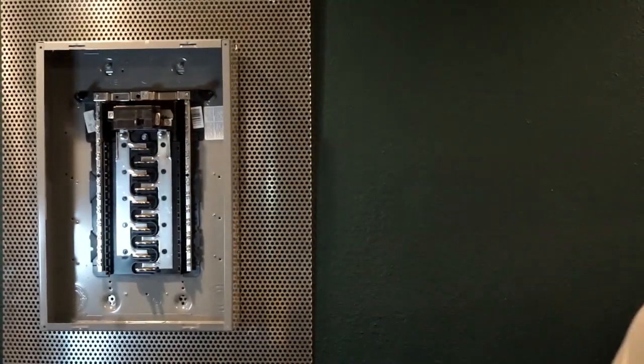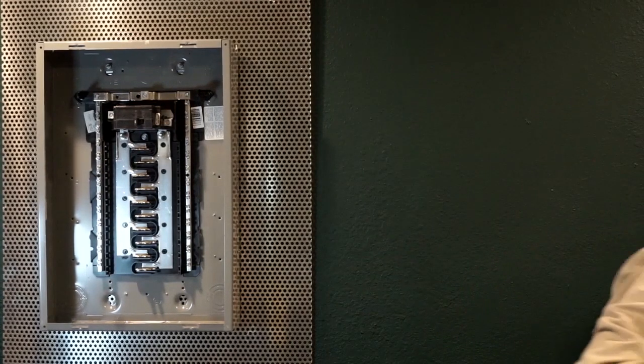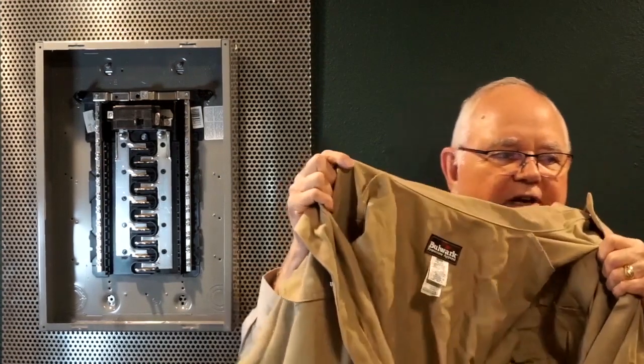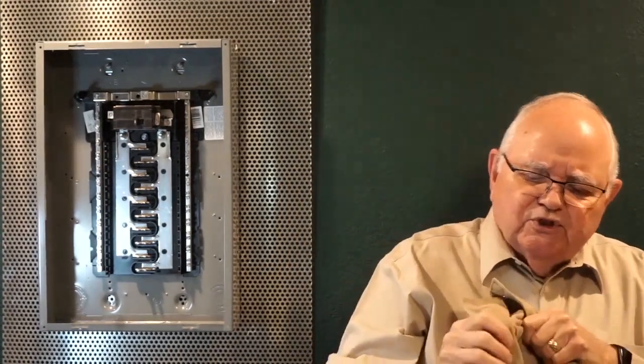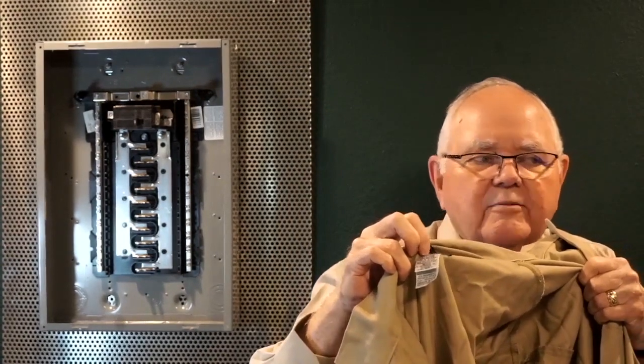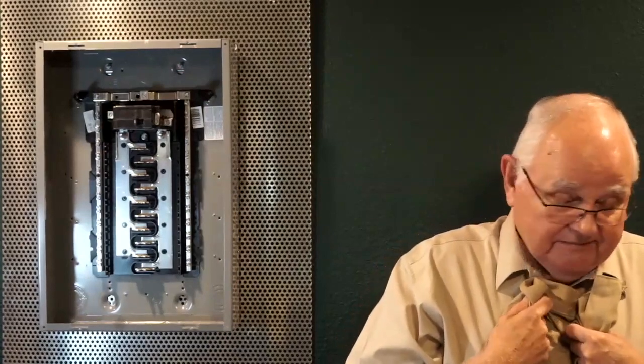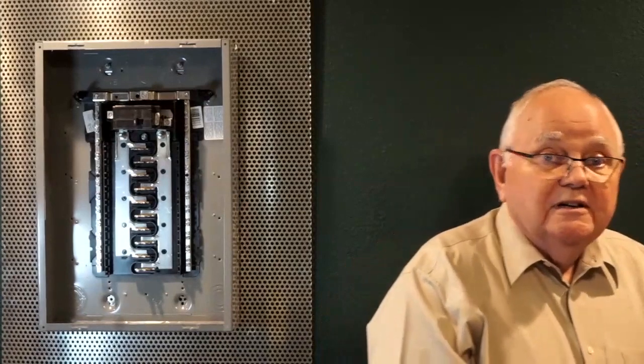Okay. When it comes to the arc rating on your clothing, you will not only want to inspect your clothing to make sure that there is no physical damage to it and so forth, and it's not grease or oil on it and anything like that, but for sure you want to inspect the label. And the thing that I'm looking for in the label, one of two things. I'm either looking for an ATPV value or an EBT value. This one says ATPV, 10.6 calories per square centimeter. That means that this is designed to protect me up to a 10.6 calorie arc then. Important information. So make sure that you properly select your PPE, okay? The same is true in my gloves. Make sure that your gloves are voltage rated for whatever the particular equipment is that you're going in to work on then. So we select our PPE.